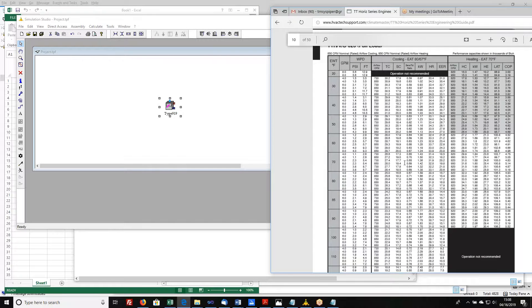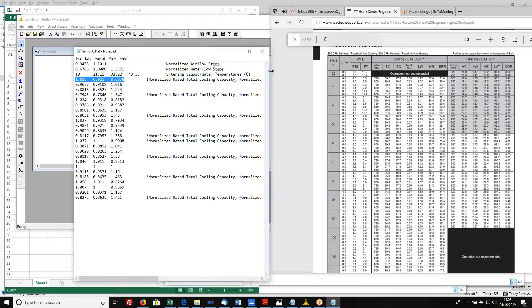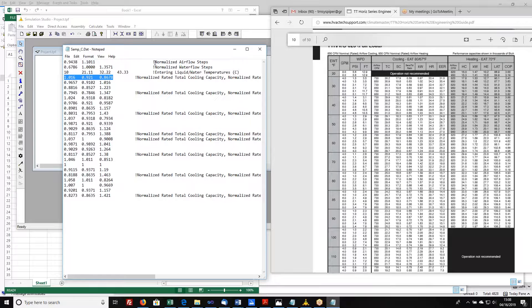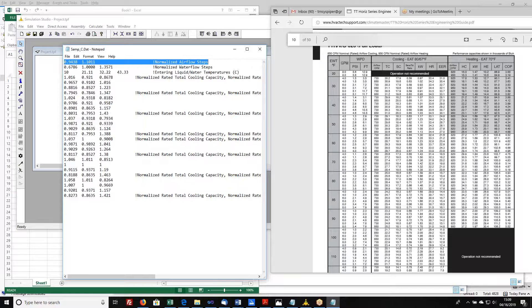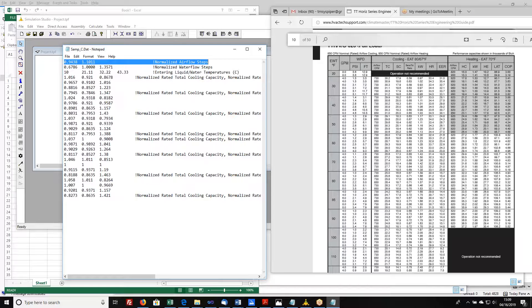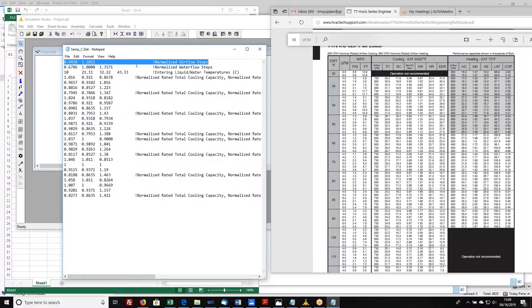This is the kind of data file that is typical of heat pumps. I'm going to show you how to translate this into the data file that we need. Referring back to the data file for just a moment, you'll notice that the first independent variable is the normalized air flow steps. That's an indication that this heat pump can operate at two different air flow rates. And if we look over here, there's a column in the heating mode called air flow CFM. And here in the cooling data, there's a column called air flow CFM. And you'll notice that each time there are two values, 730 CFM, 850 CFM, and then it repeats 730, 850. So this data file, like the one that is the example data file, has got two air flow rates in it. So we're going to end up with two values here.